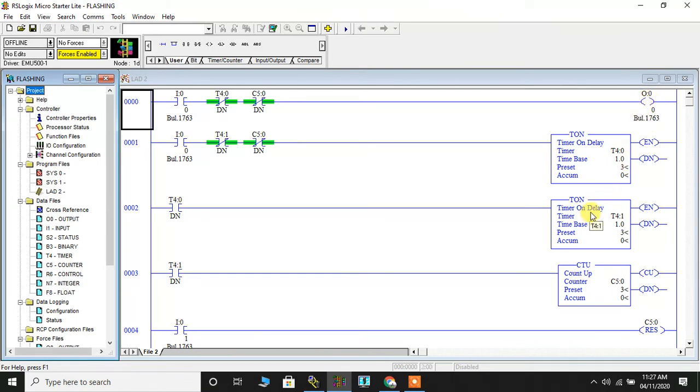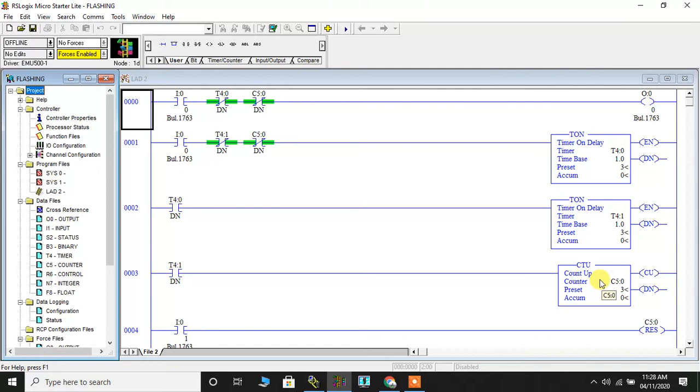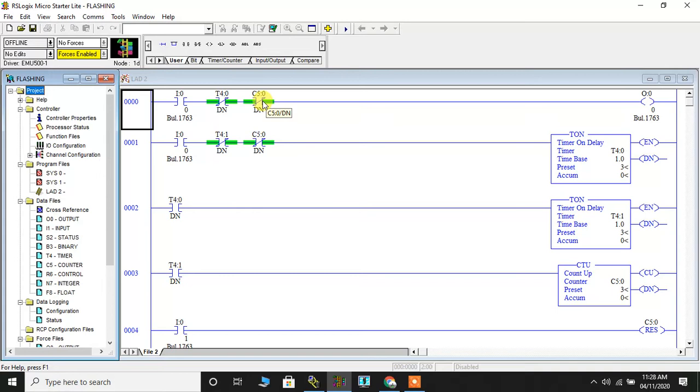Every time the on delay is complete your counter will be incremented by one. I am going to count this process for three cycles. After three cycles are done the circuit will get disconnected because the done bit, the normally close contact of done bit of the counter, is placed in the first and second rung which will eventually cut off the supply to the lamp and the timer.